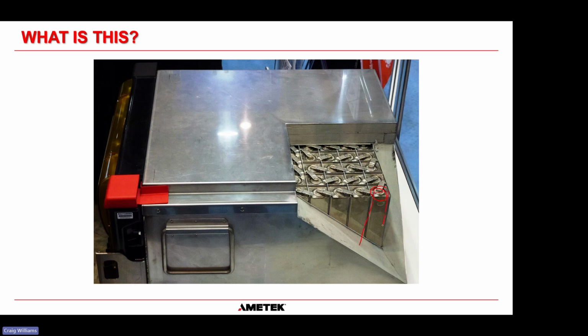So this cuboid here, I would say that's a cell, and they connect them in series and parallel inside this module to get the capacity and the voltage that they require. And you can see, if you look here, this is actually insulation material. It's high density foam to insulate it. So there is a heater inside this salt battery module that heats up these cells to melt the salt. And then there is really thick insulation to keep that heat in as much as possible for efficiency purposes. So a large portion of the module size is taken up by that insulation.